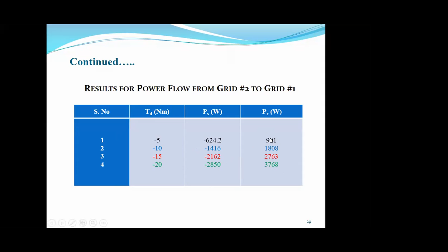This graphical view shows that at 0 Newton meter, both powers were positive, so no power flow was taking place. As I applied torque in the positive direction, grid 1 power becomes more positive while grid 2 power becomes more negative, meaning more power starts flowing from grid 1 to grid 2. As I apply negative torque, grid 2 power becomes more positive and grid 1 power becomes more negative, so by applying negative torque, the power flow from grid 2 to grid 1 starts increasing.